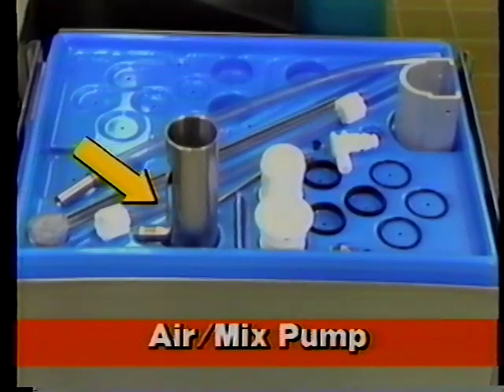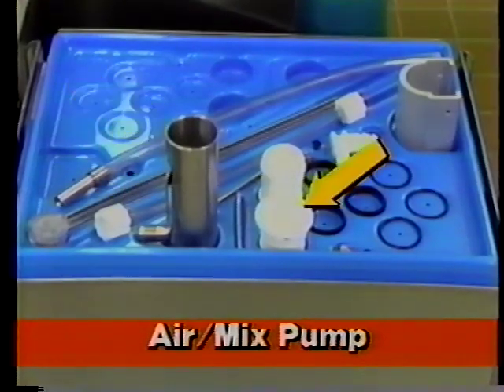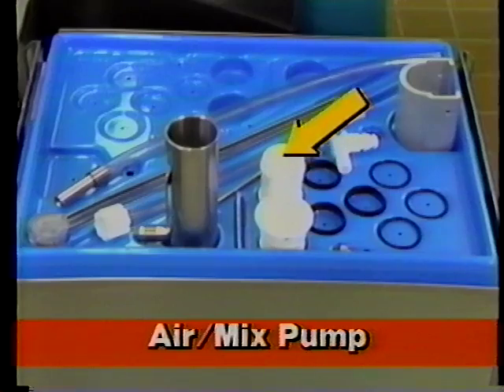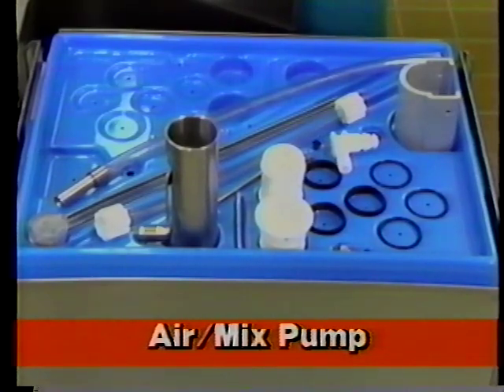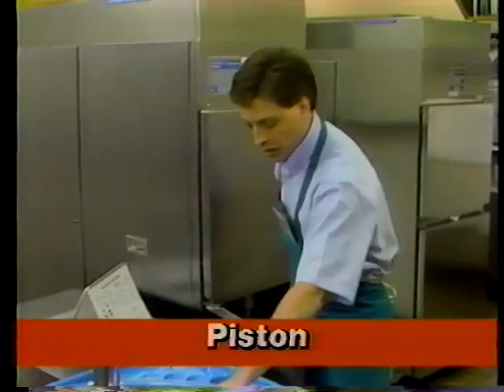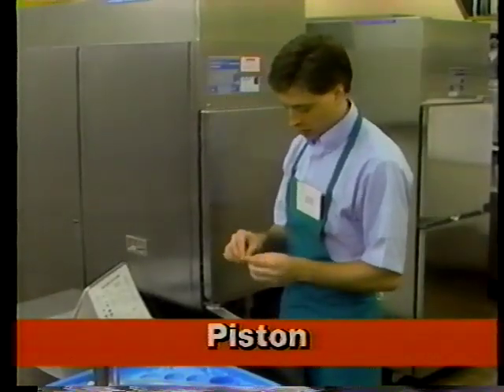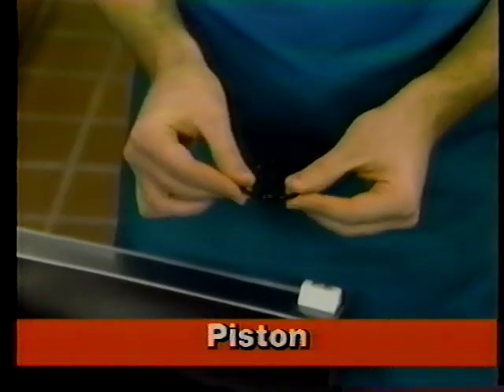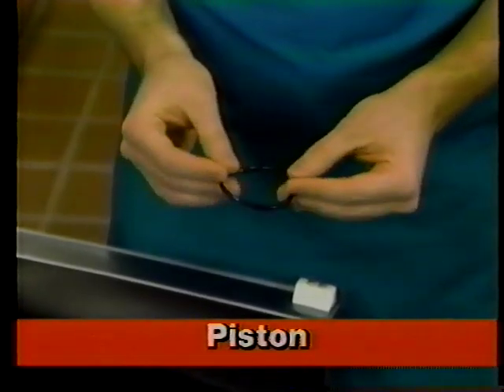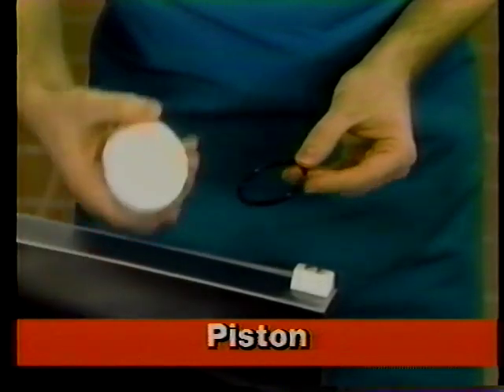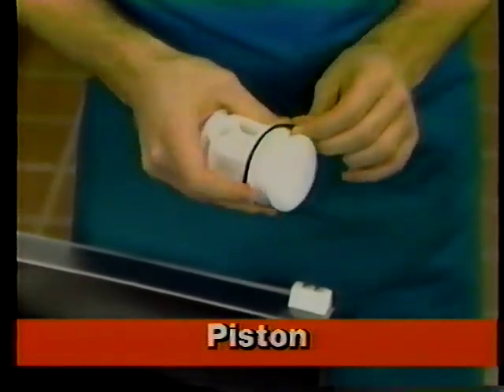The large metal part is called the pump cylinder. The 2 white plastic parts are the liquid valve body with the flange on the bottom and the piston with the hole in it on the top. You need to add some parts to the liquid valve body and the piston, and then put them both inside the pump cylinder. Start with the piston. The piston needs an O-ring installed, and as before, check the O-ring. If it's okay, slip it over the end of the piston and into the groove.